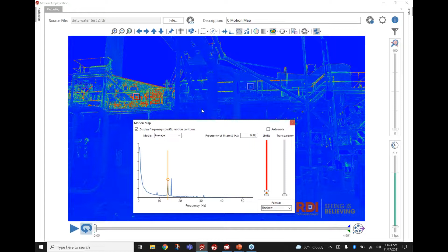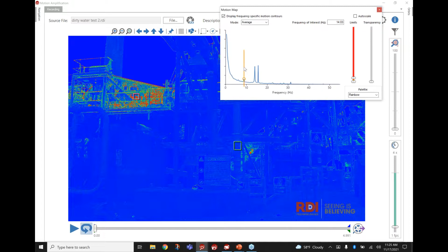But all that to say, think about this being on a floor with motors and pumps out in the factory or your facility, and nearby pumps can induce vibrations, or nearby motors can induce vibrations on neighboring machinery. So being able to do root cause, and track down where these vibration paths are coming from and what's causing what to vibrate. And then of course, if we show the pump here, we can see all that red, which is where that was vibrating when we filtered it, right? So we can measure, and then we can do this motion map. So this is frequency and amplitude.